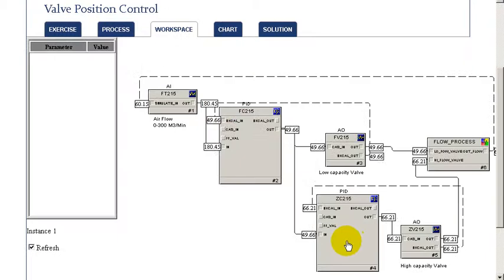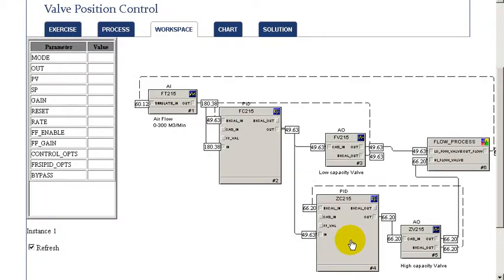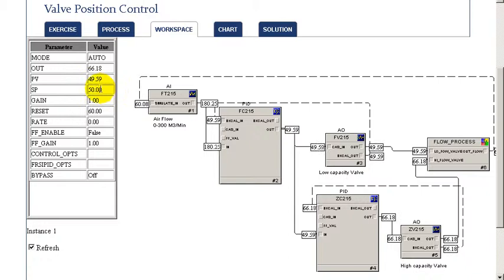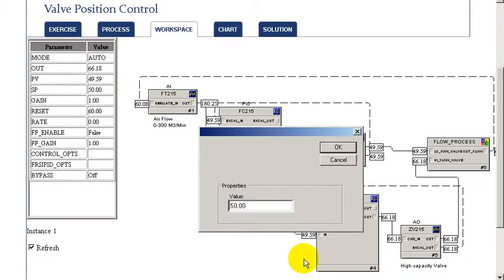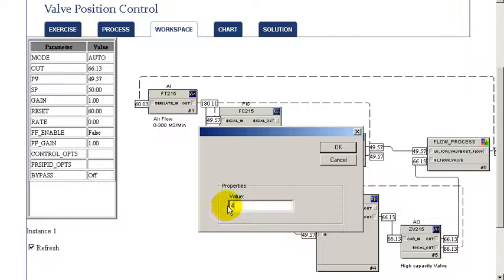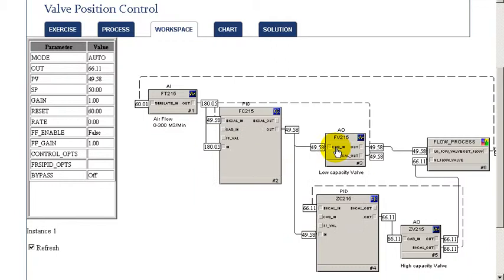Next, we'll actually change the target for the valve position controller. Normally, you'd like that at about 50% of range. In this case, we're going to change that by about 10%. And look at the impact of that in terms of the way the small valve is regulated and the larger valve.